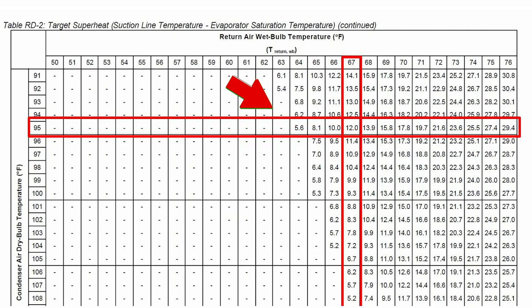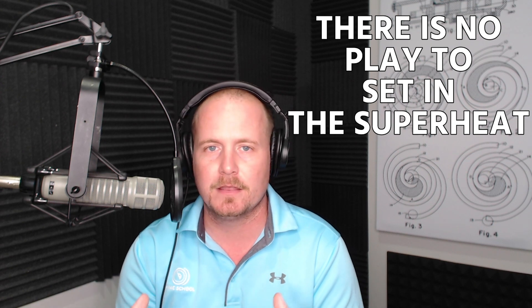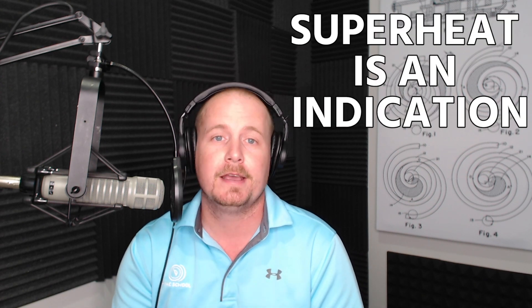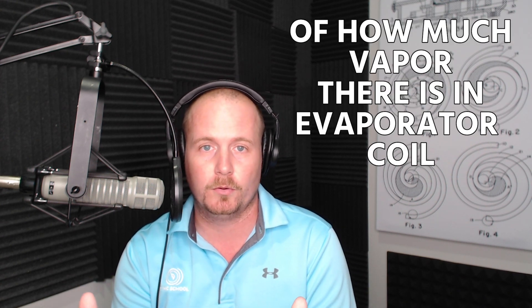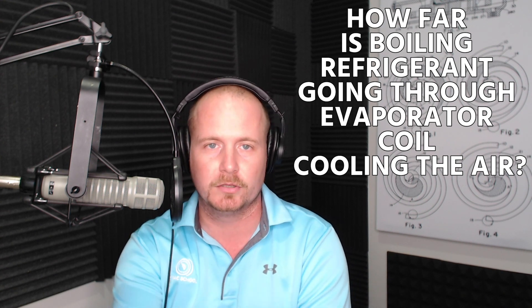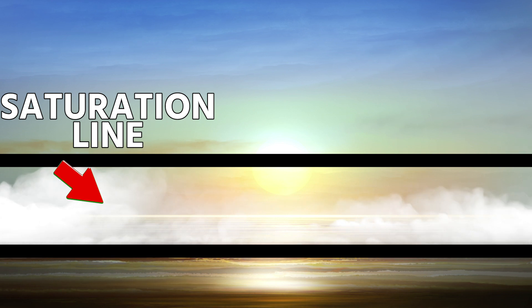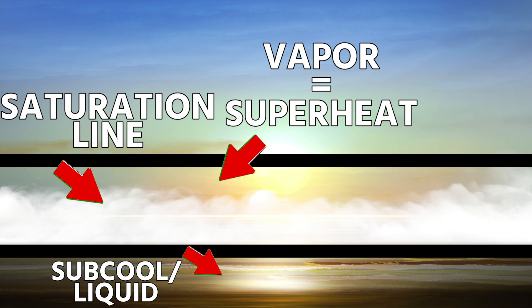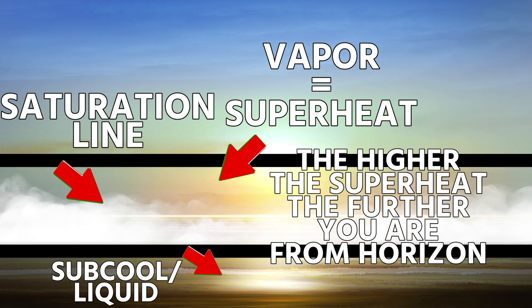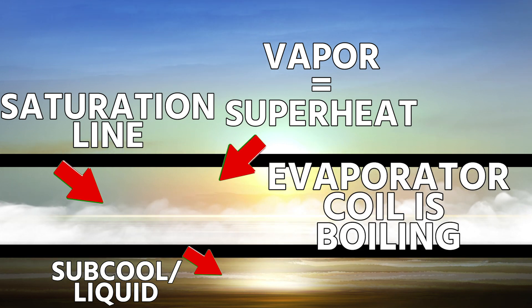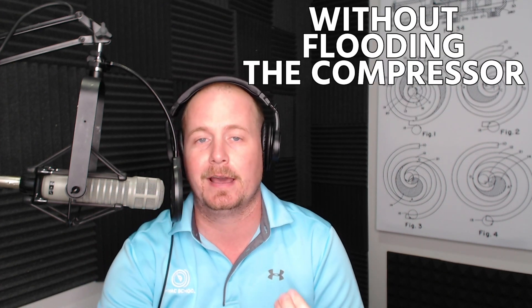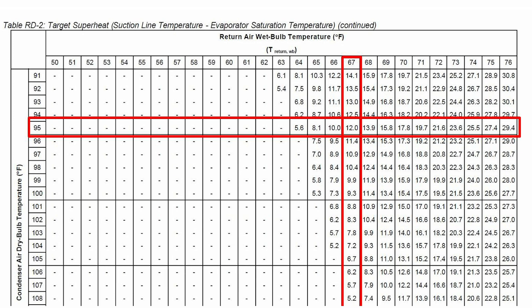Now let's talk about what causes the target to change. Looking at this chart, if we keep the 95-degree outdoor temperature static and the indoor wet bulb temperature increases, the target superheat also increases. With a fixed metering device, you have no ability to adjust the metering device to set superheat. Superheat simply indicates how much vapor is in the evaporator coil — how far the boiling refrigerant is traveling before picking up sensible heat. Using the horizon analogy: vapor is above the ocean, liquid is below it, and higher superheat means you're further from that saturation line.